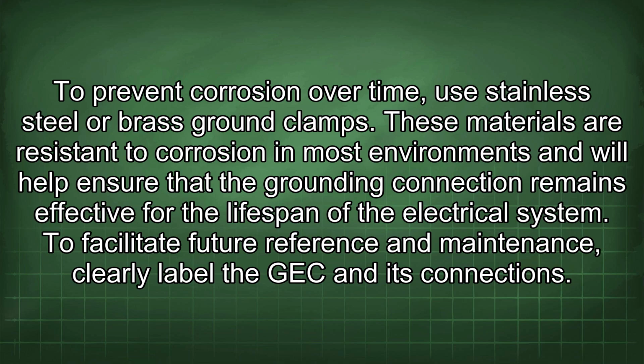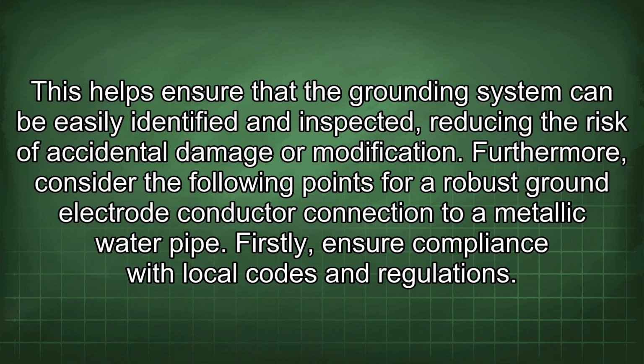To prevent corrosion over time, use stainless steel or brass ground clamps. These materials are resistant to corrosion in most environments and will help ensure that the grounding connection remains effective for the lifespan of the electrical system. To facilitate future reference and maintenance, clearly label the GEC and its connections. This helps ensure that the grounding system can be easily identified and inspected, reducing the risk of accidental damage or modification. Furthermore, consider the following points for a robust grounding electrode conductor connection to a metallic water pipe.